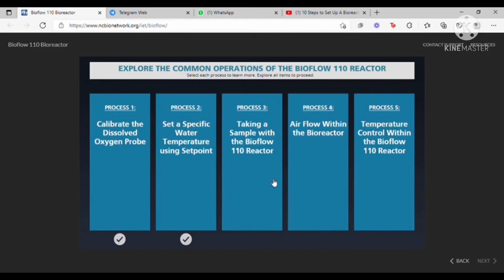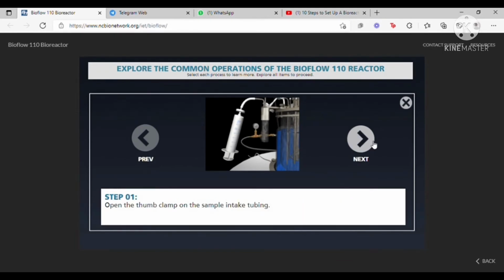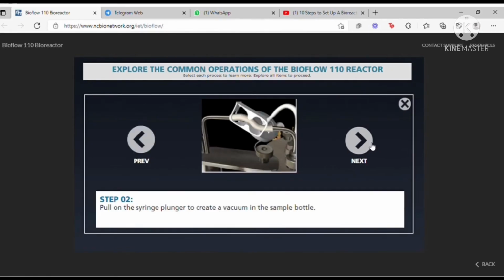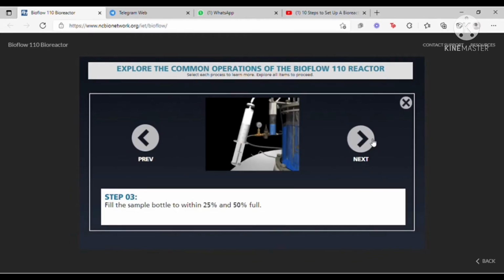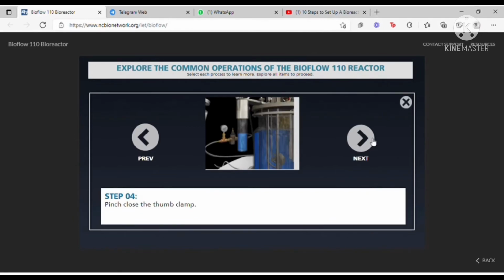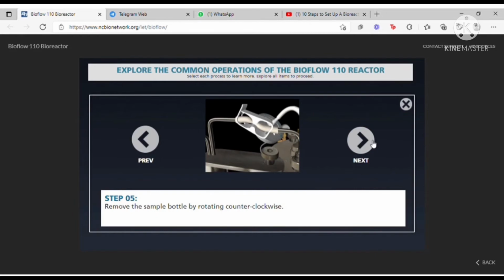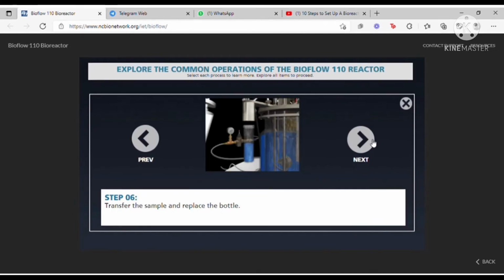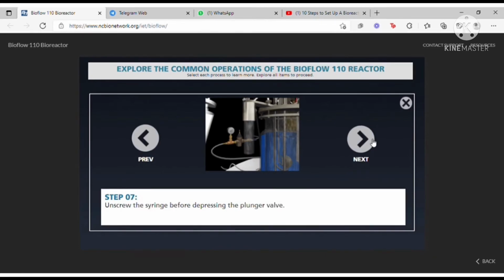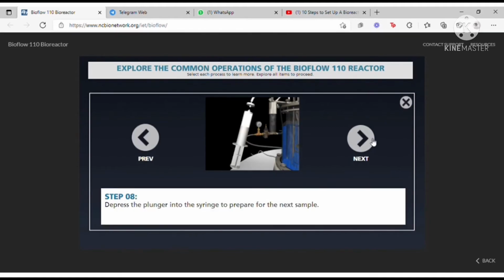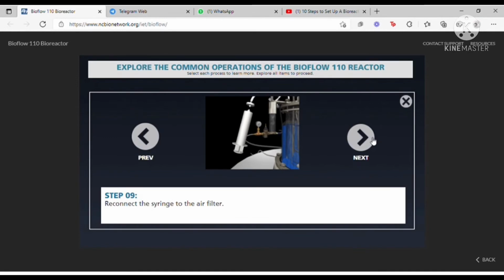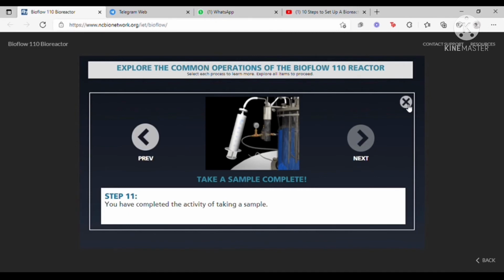Next, we will move on to process 3, which is taking a sample with the Bioflow bioreactor. Step 1 would be to open the thumb clamp on the sample intake tubing. Step 2 would be to pull on the syringe plunger to create a vacuum in the sample bottle. Step 3 would be to fill the sample bottle to between 25% and 50% full. Step 4 would be to pinch close the thumb clamp. Step 5 would be to remove the sample bottle by rotating counterclockwise. The following step would be to transfer the sample and replace the bottle. Next would be to unscrew the syringe before depressing the plunger valve. Then depress the plunger into the syringe to prepare for the next sample. Reconnect the syringe to the air filter. And lastly, we have completed the activity of taking the sample.